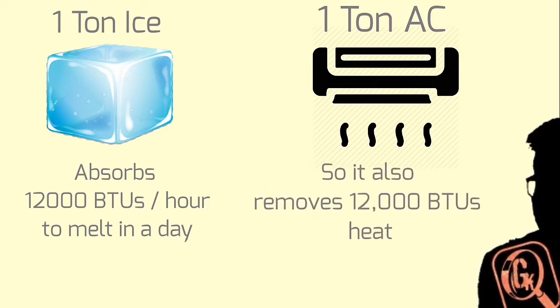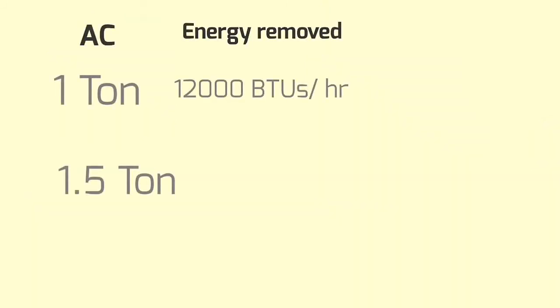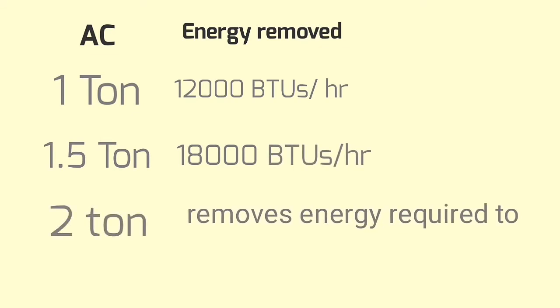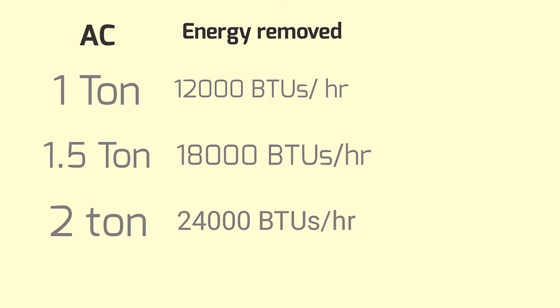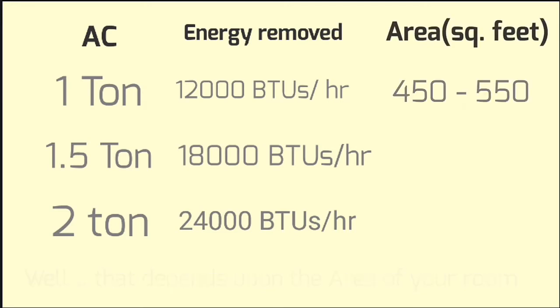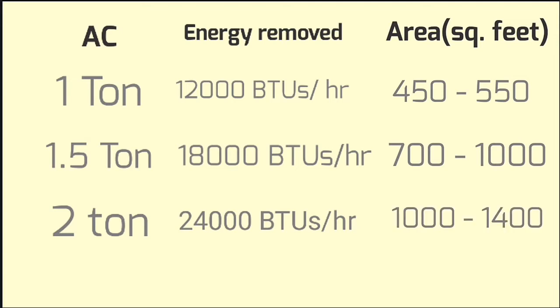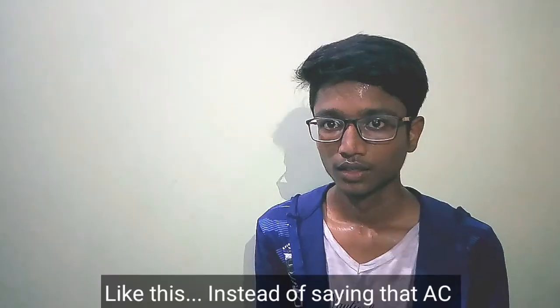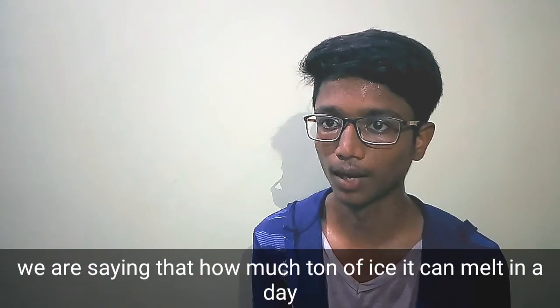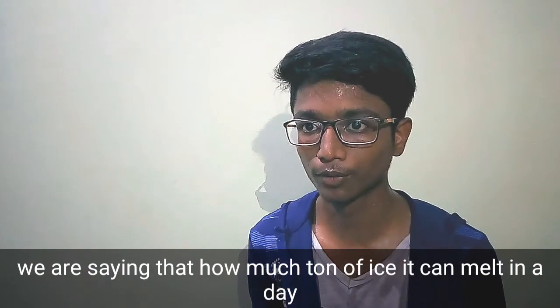1 ton AC absorbs 12,000 BTUs per hour. 1.5 ton AC is 18,000 BTUs per hour. 2 ton AC is 24,000 BTUs per hour. For room area: 1.5 ton AC is suitable for 700–1000 sq ft, and 2 ton AC is for larger areas.